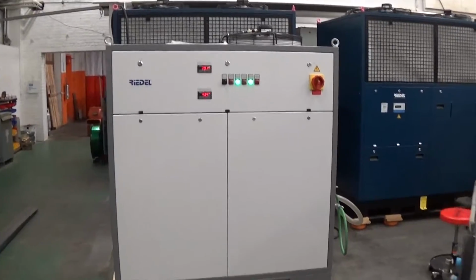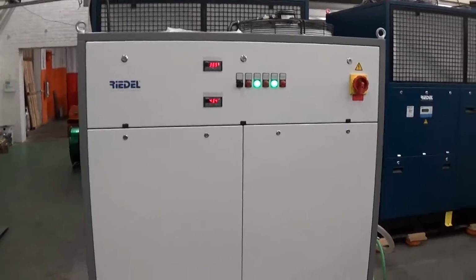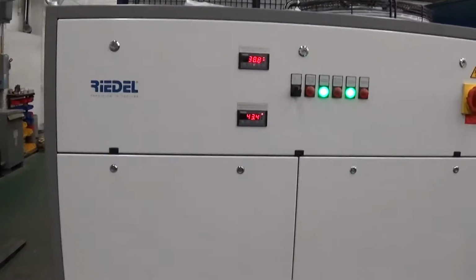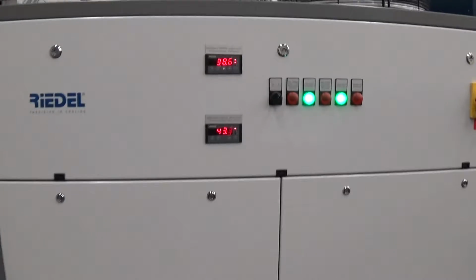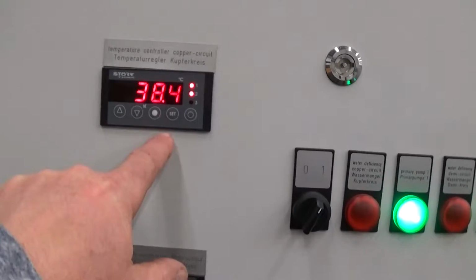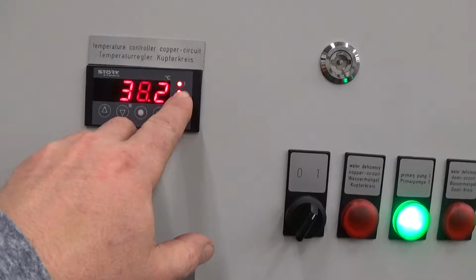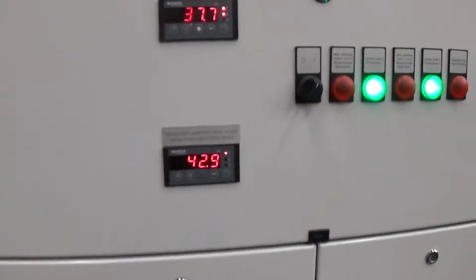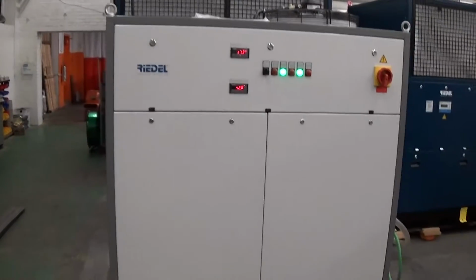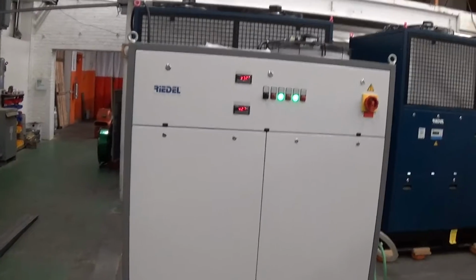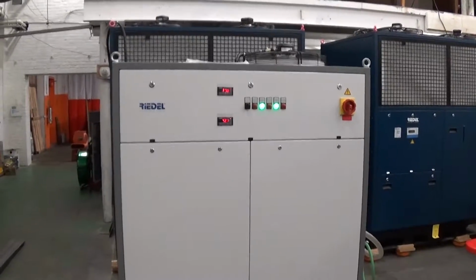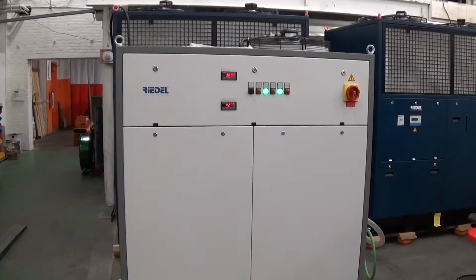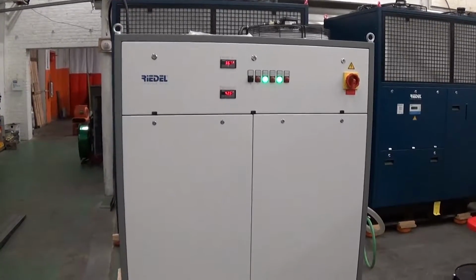Here's our video number 2 after the built-in delay kicked on. We got both compressors going and chilling right now. That's indicated by the top controller showing light number 1 and light number 2 on. On the bottom controller, light number 1 is showing that solenoid valve is on, calling for cooling also. Interestingly enough, and the way it is supposed to behave, at the slightly higher temperatures that I had brought the tank up to here, over 40 C, with the side covers off, that was enough absence of airflow that it did go into high pressure alarm.